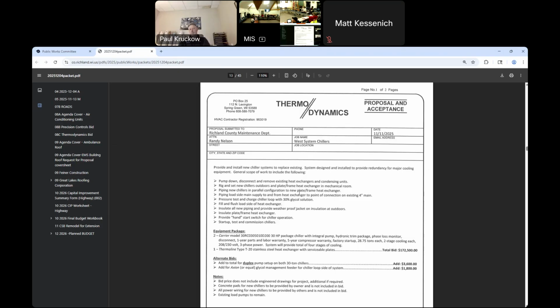We'll require two power supplies outside, but even with the multi-stack, you'll require power running to the condensers outside and power to the chiller inside and so on. The Carrier chiller, I believe it says on there, does have a single point power connection. So basically the electrician, once he gets outdoors, sets a J-box and whip up to it. The chiller itself has a disconnect on it. The reason I mention that is it eliminates some electrical cost from the electrician. He's got to put in a 50 amp 3-phase disconnect or 60 amp that's built into the machine.